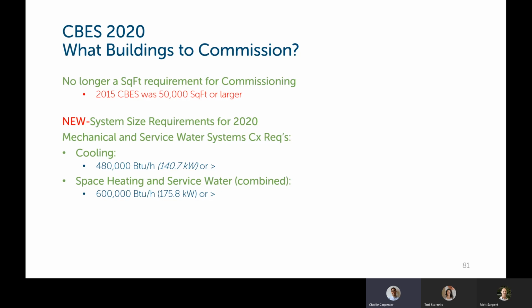So for a cooling system that is greater than 480,000 BTU per hour, that's 140 kilowatts, any cooling system larger than that would need to be commissioned. And if both the space heating and service water, domestic hot water systems combined capacity is 600,000 BTU per hour or more, then you'll need to commission that system. So both of those are going to make it a lot more common for buildings to require commissioning for the 2020 commercial code.